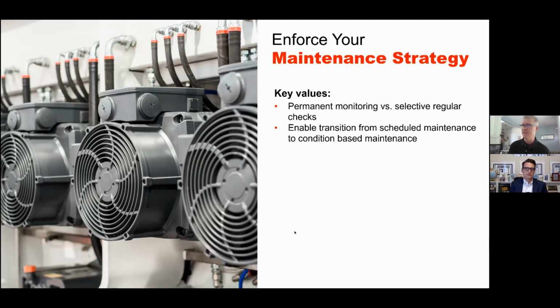It's a cost-effective solution versus an external third party. Sure, there are other people that have sensors and everything you can put on equipment, but you have to tie all those together, which means you have a learning curve to program all those. You have to make sure your wiring and everything's proper. Where you place those could be critical. There's so much involved in combining multiple products. As an ex-panel builder, a UL panel builder in a UL shop, I can tell you with great honesty, where you place things is extremely important, especially in a panel or on a machine. If you place something next to a welder, you're going to have all sorts of issues. Any type of high voltage next to low voltage, or these types of communication levels of voltages, major issue. You can blow components up. So that's a big thing.